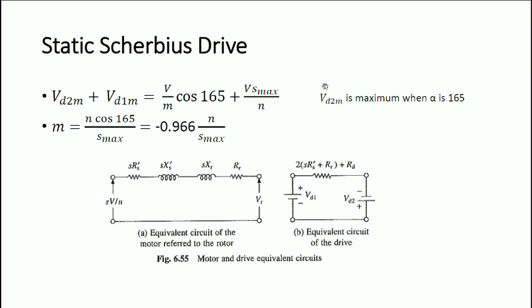The turns ratio M = −0.966·N / S_max. So the turns ratio of the transformer depends on the turns ratio of the motor N, which is fixed once you select the motor, and on S_max — the maximum slip — which is determined by the minimum speed required for the drive. These are the two criteria for selecting M.